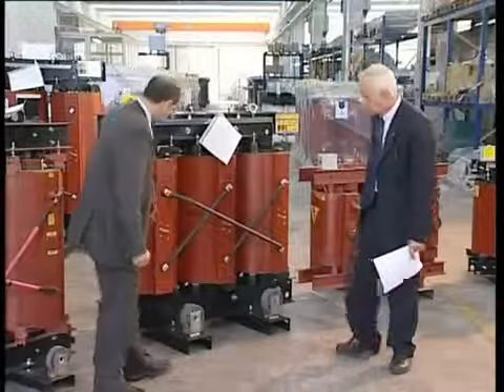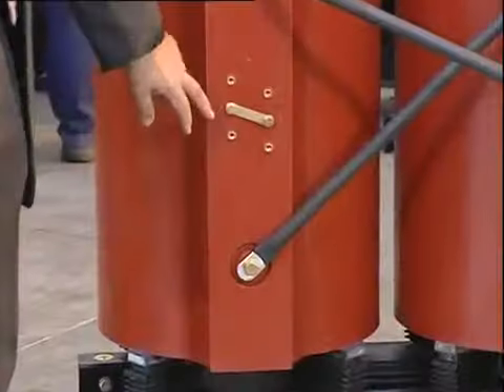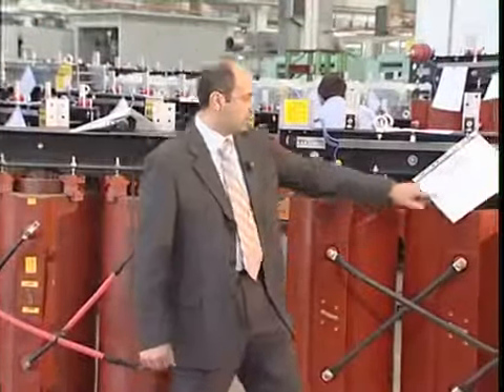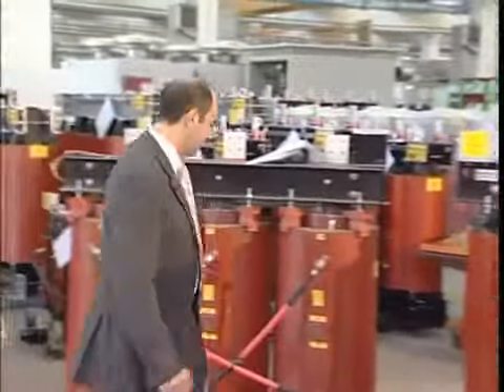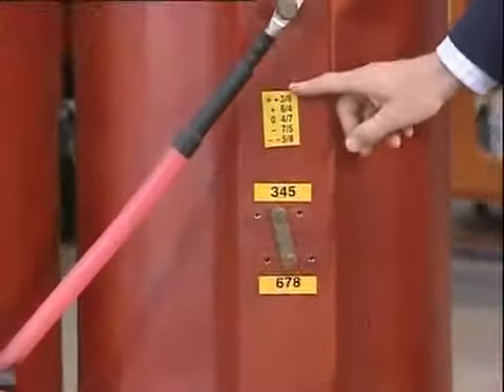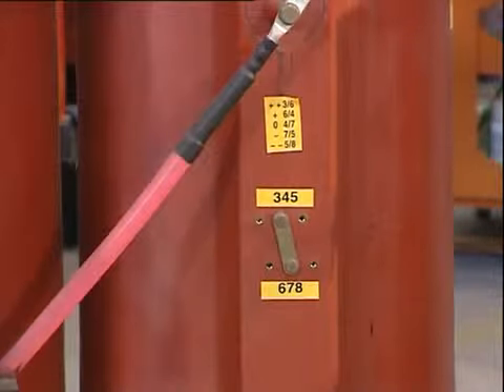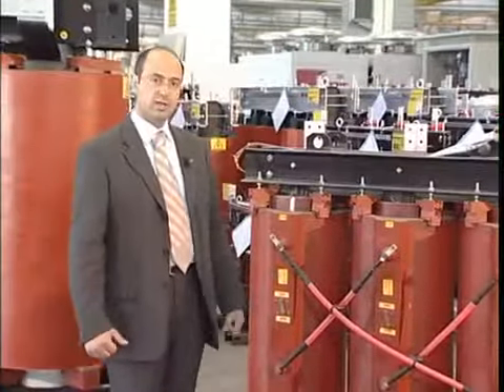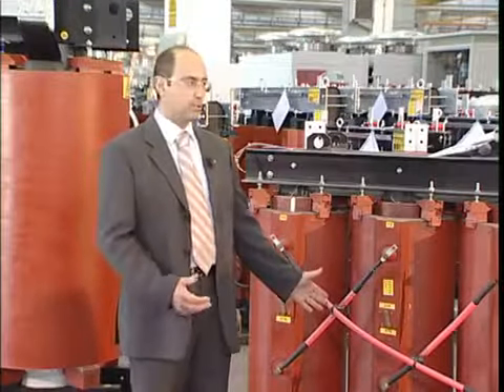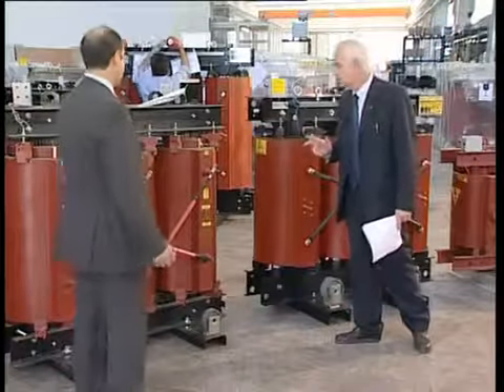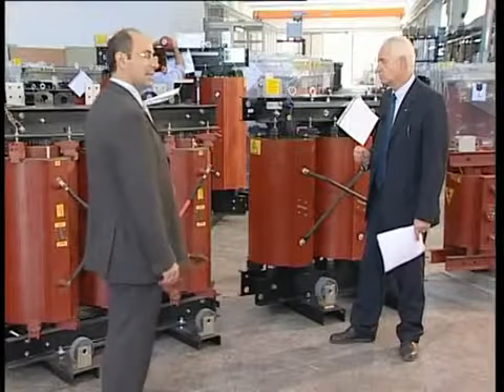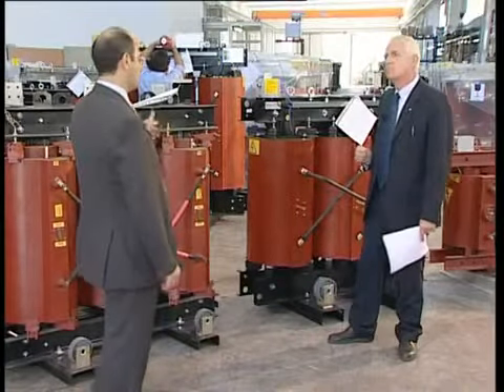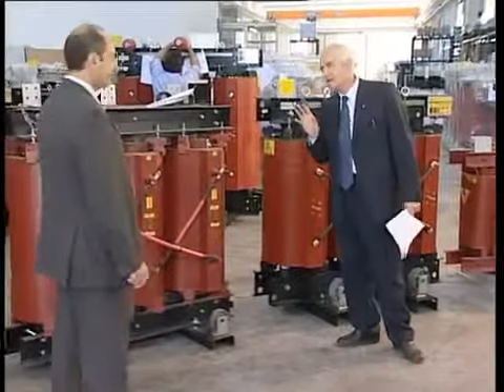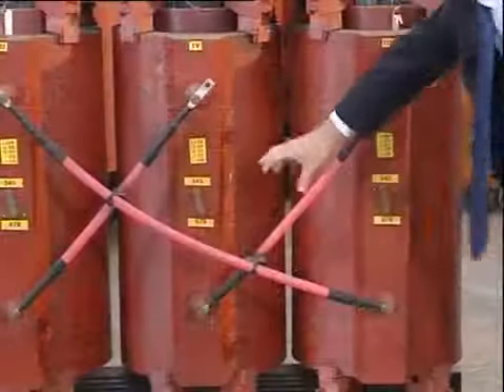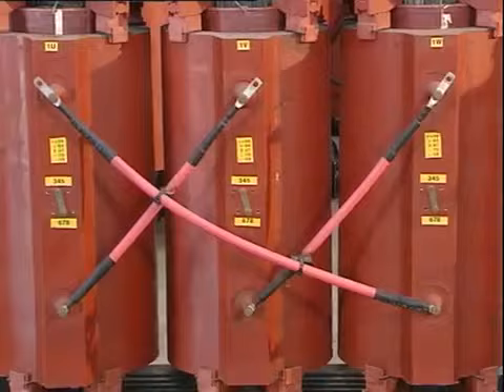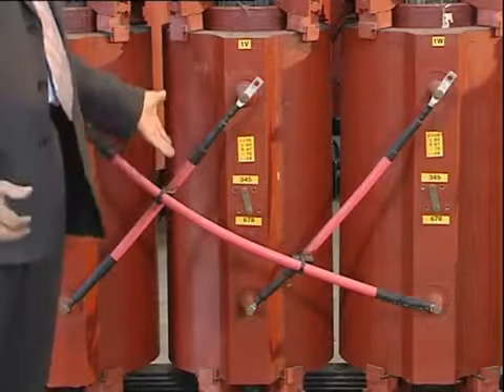All right, let's have a look. We can immediately see the adjustment system, where the numbers have been pre-stamped on the winding column and specified on the plate. And in the other case? Conversely, in this case the numbers have been simply printed on some labels, which, luckily, have not come off. Also because this transformer, manufactured a couple of years ago by one of our competitors, worked just over a week and then... What happened? It failed because of an electric discharge between the 20 kilovolt medium voltage winding and the low voltage one. Therefore, this transformer is cheaper, but its value is considerably lower too. Yes. Let us consider some other aspects. This already does not look good to me. The triangle connection looks like a make-do solution, wrapped together after combining different materials.